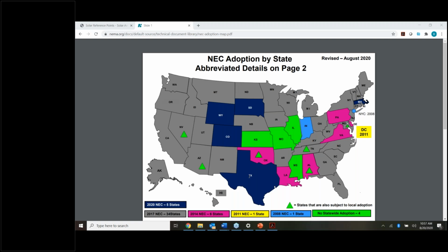When anyone's doing an electrical project, it is an opportunity for the jurisdiction to review the grounding electrode system of the house. And if that grounding electrode system is inadequate, which over the years in older houses, in many cases, the answer is yes, it is inadequate, then it needs to be improved. But it's not just because it's solar, it's because that's a basic requirement. And so as long as you get that grounding electrode system up and going correctly, then our attachments of the grounding electrode to it are safe, are good, and there's no need for any more than a good grounding electrode system, if that makes any sense. And that would be consistent with the 2014 code.